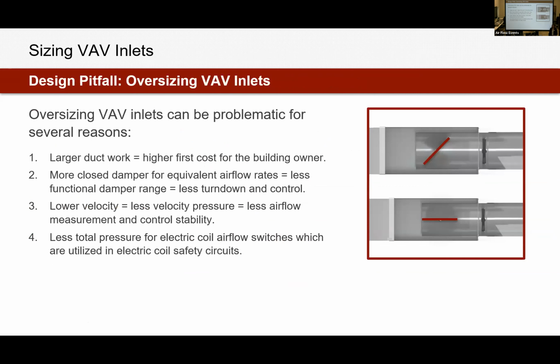All right. So I've been in too many engineers' offices when they're sizing single ducts and they tell me, we'll determine what it needs to be and then we'll just upsize it to make sure we're safe. That could be problematic. Sometimes it is okay and you are on the safe end, but depending on what those airflow ranges are, you could actually be making a bigger issue. So if we are oversizing an inlet valve, for example, in that last example, if we went to a 10-inch inlet, we are adding larger ductwork to our building. So if we do that for every single box, we've got larger ductwork, increasing cost and potentially labor.